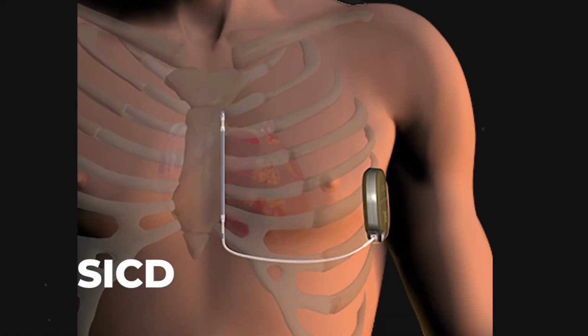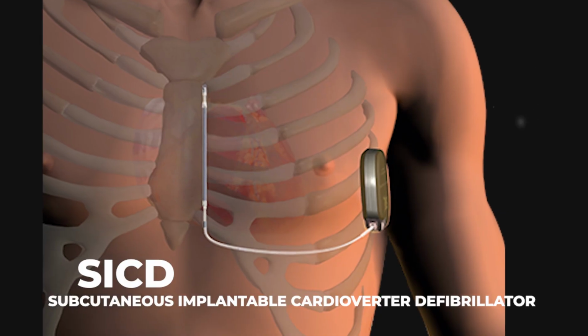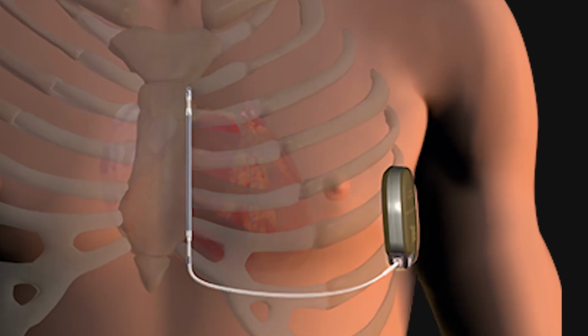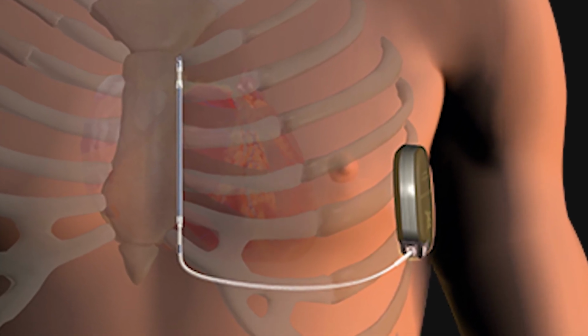The second type we discuss is the one that Leslie's daughter has, which is the S-ICD, or Subcutaneous Implantable Cardioverter Defibrillator. And unlike the traditional ICD, this device has no wires inside of the heart. Instead, the generator or battery pack is placed under the skin on the left side, typically like a hand's width below the armpit. And a single lead is tunneled under the skin along the left side of the breastbone, just above the sternum. Because the lead and generator sit outside the rib cage, the device needs to deliver a little more energy than the Transvenous ICD, but still much less than an external defibrillation, usually about 65 to 80 joules, depending on the manufacturer. One of the biggest benefits of the S-ICD is that there are no intracardiac leads, which reduces long-term risk like infection or lead fracture.